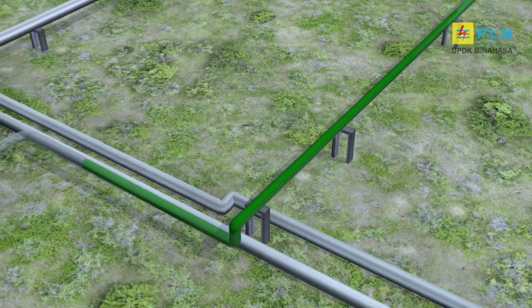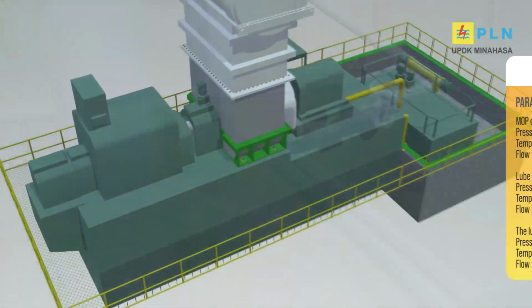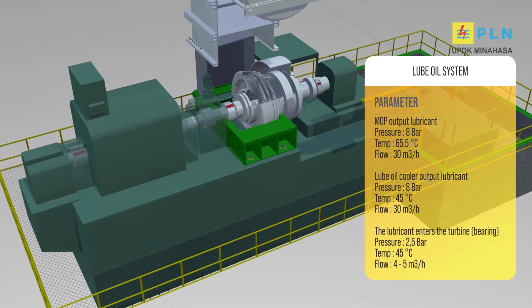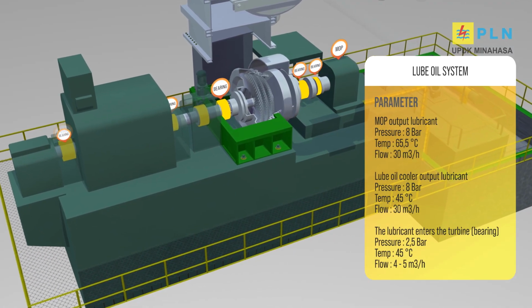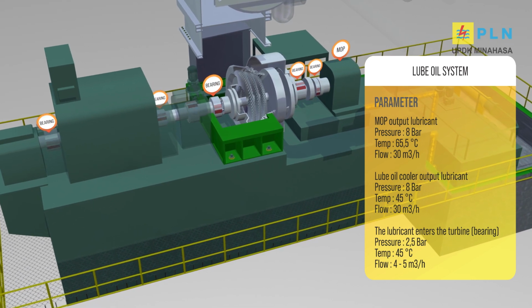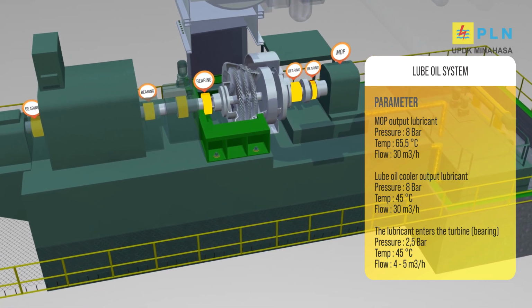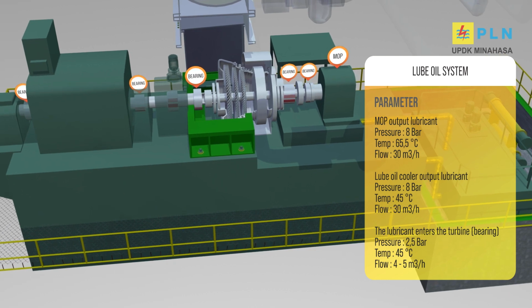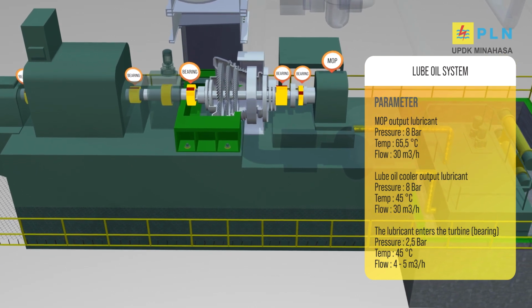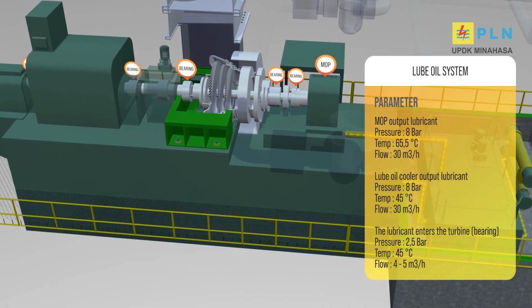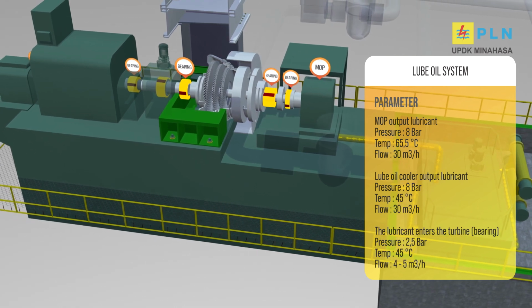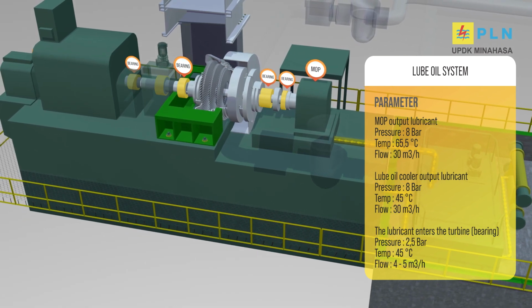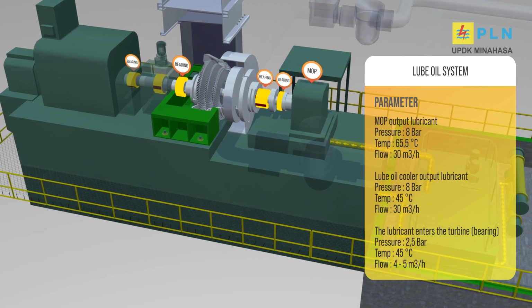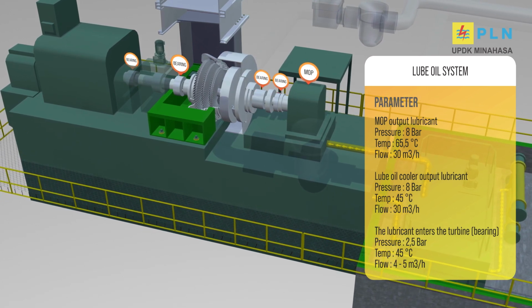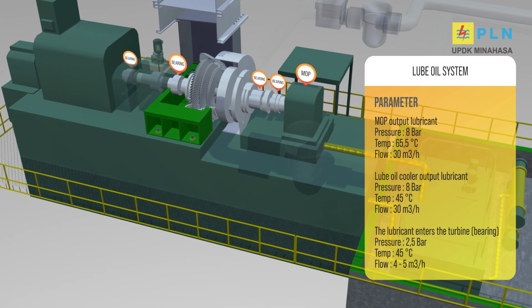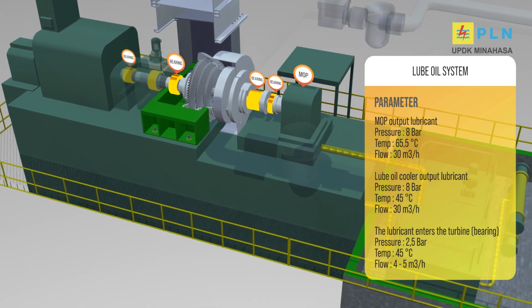In addition to the cooling system, there is also a lubricant system that functions to lubricate turbine bearings. The lubrication system is supplied from the lube oil tank, then the pressure is increased with a main oil pump or MOP of 6 bars. Then it enters the lube oil cooler, a shell and tube type, where the temperature is reduced from 65.5 degrees Celsius to 45 degrees Celsius. Then it is distributed to each turbine bearing and recirculated to the lube oil tank.